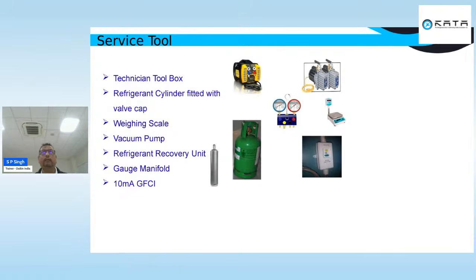But from my side I'll advise that once you recover the refrigerant, even with good equipment, please do not charge it again, because once it comes out it won't give you the same properties the refrigerant had. So a recovery machine should be used. Manifold gauge: for R22, R32 and 410 you can use the same manifold gauge, but the charging pipe should be different for R22, for R32, and for 410. Today most technicians use the same charging pipe, and their charging pipe is not proper.